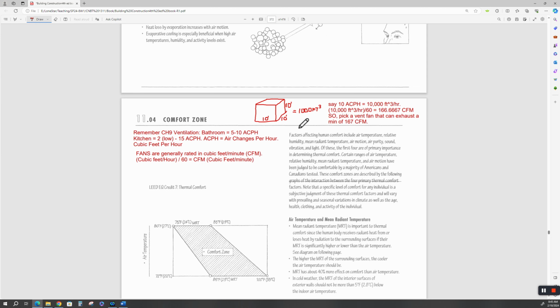So here's a calculation up here I did before. So let's just assume we have a 10 by 10 by 10 foot space. So that's 1,000 cubic feet. And we want, let's just say we want 10 air changes per hour. Well, that's 10,000 cubic feet per hour.